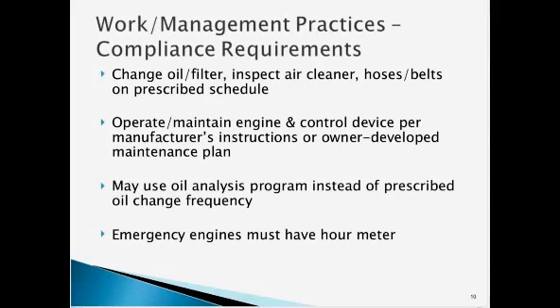You can use an oil analysis program to extend the frequency for doing those oil changes. So say your frequency is every 1,000 hours, then once that 1,000 hours hits, you could do an oil analysis program. And if the oil parameters are within what's specified in the rule, then you can extend the oil change frequency. And also for emergency engines, they have to have an hour meter.